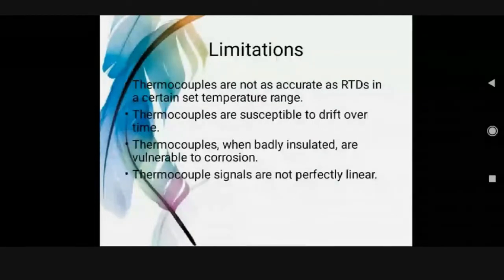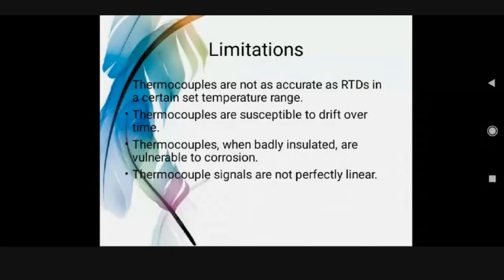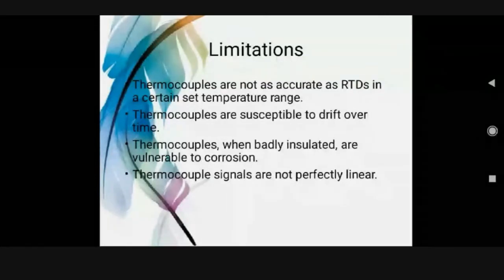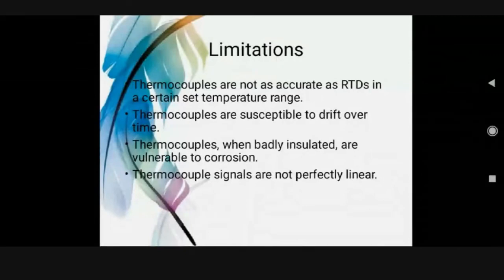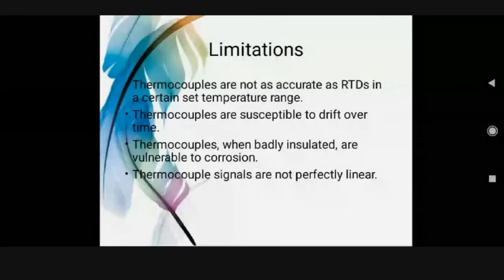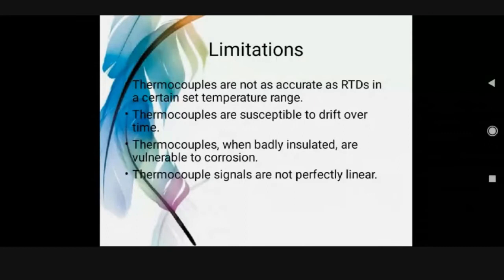Next slide. Now we will see some limitations. Thermocouples are not as accurate as RTDs in a certain temperature range. Thermocouples are susceptible to drift over time. Thermocouples, when badly insulated, are vulnerable to corrosion. Thermocouple signals are not perfectly linear.